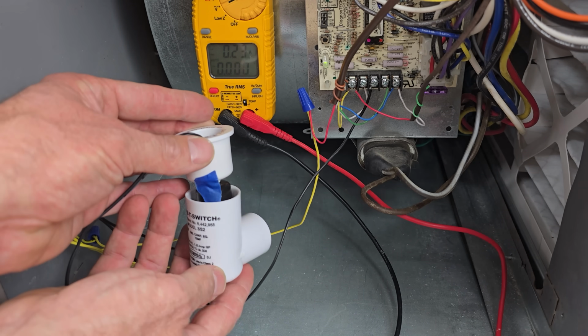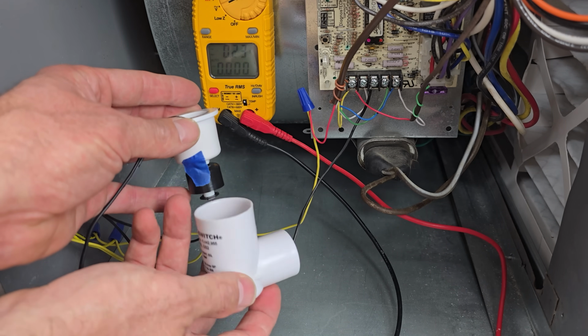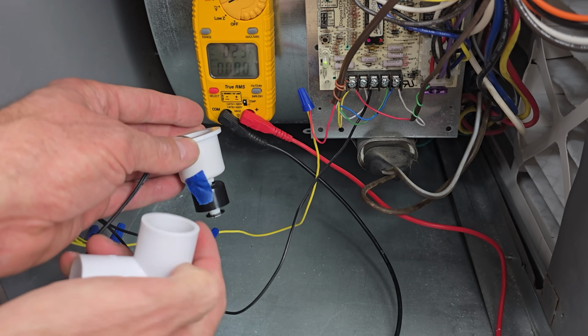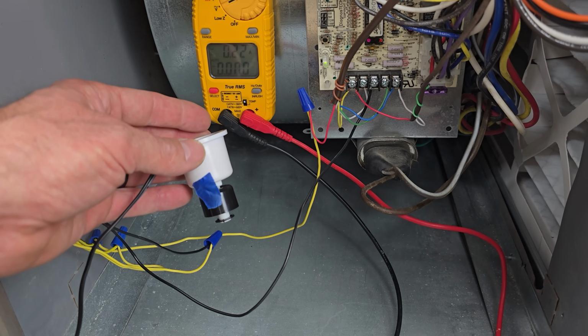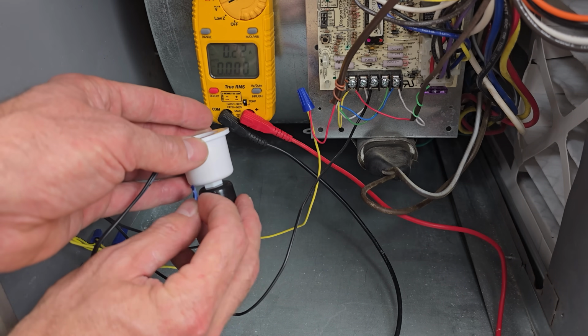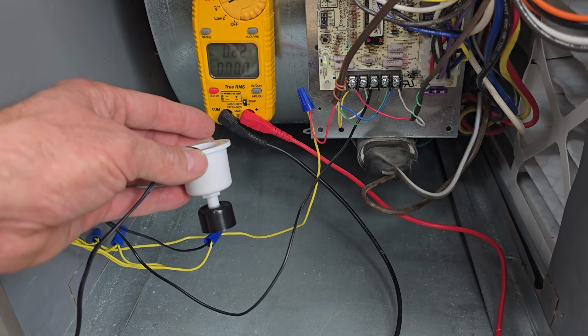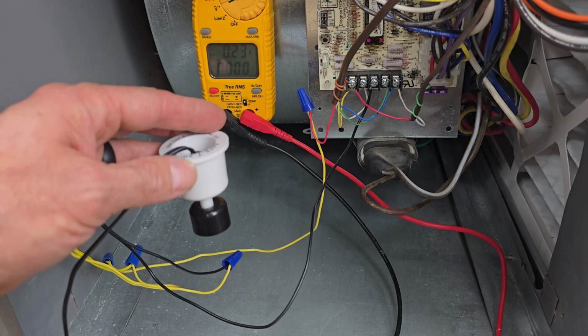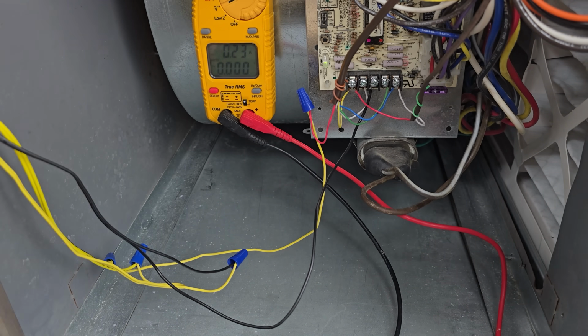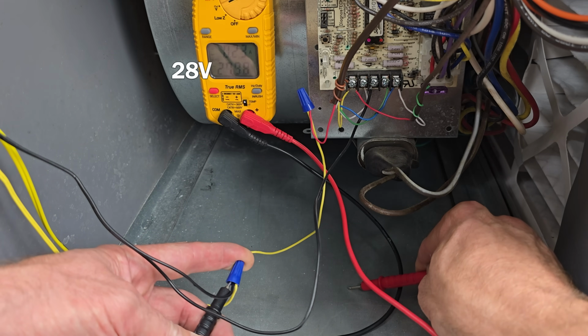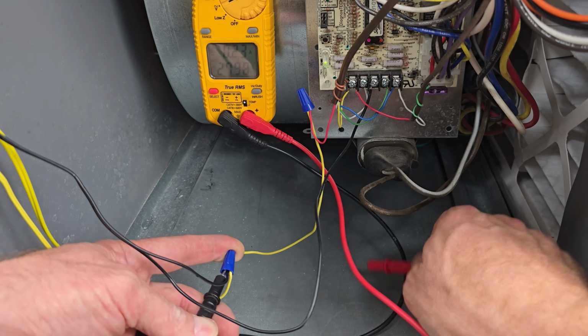So if that coil and drain line was clogged, this float is going to be in the upwards position, just like I have basically tricked out right now. When that falls down, we should now have power at that wire nut. So we're going to test it again. You see we're measuring 28 volts now, and so we are good.